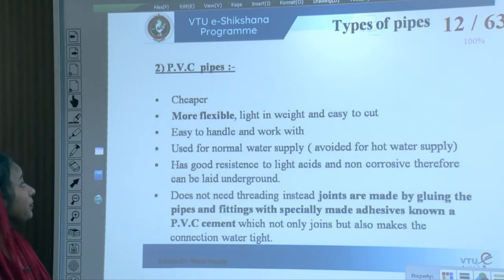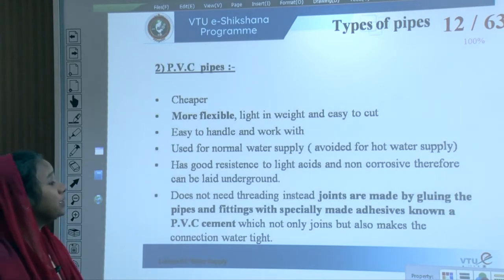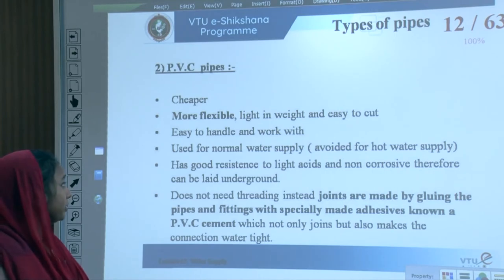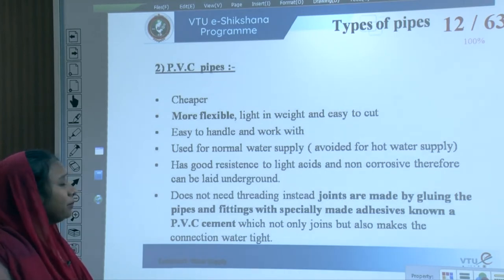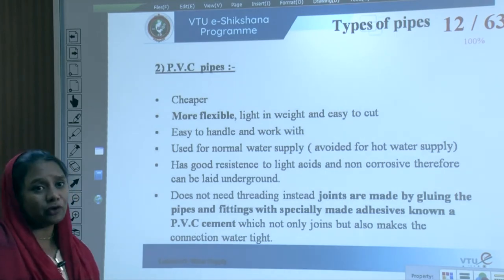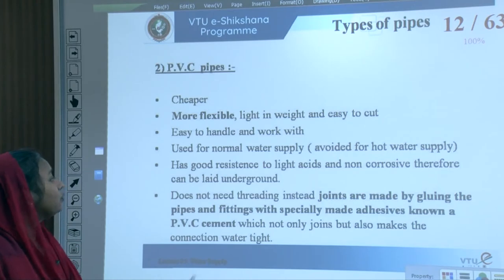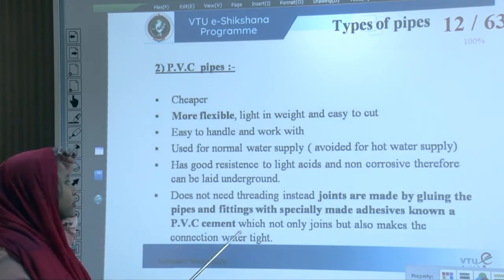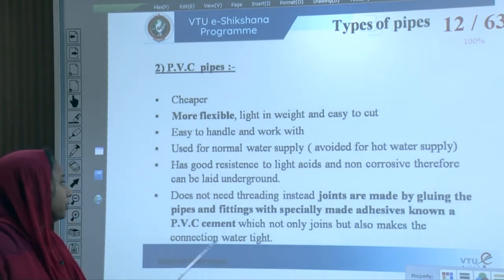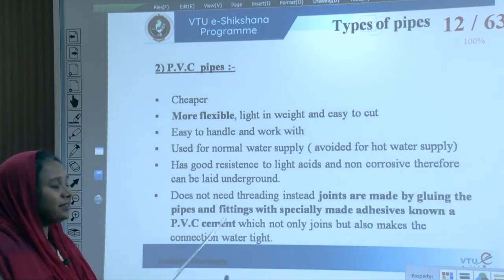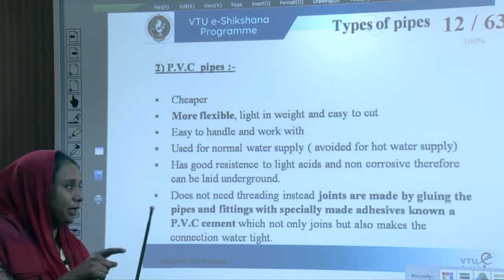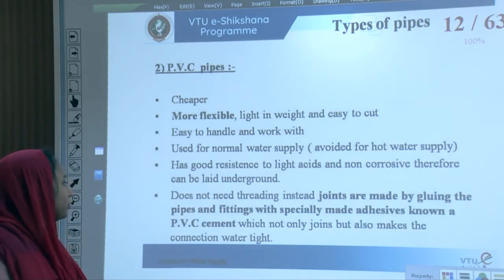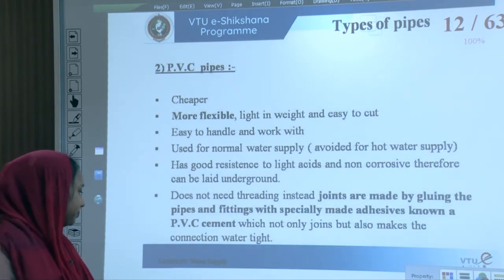PVC pipes are cheaper, more flexible, lighter in weight, and easy to cut, handle, and work with. They are used for normal water supply but avoided for hot water supply. They have good resistance to light acids and are non-corrosive, so they can be laid underground. They do not need threading; instead, joints are made by gluing pipes and fittings with specially made adhesives known as PVC cement.